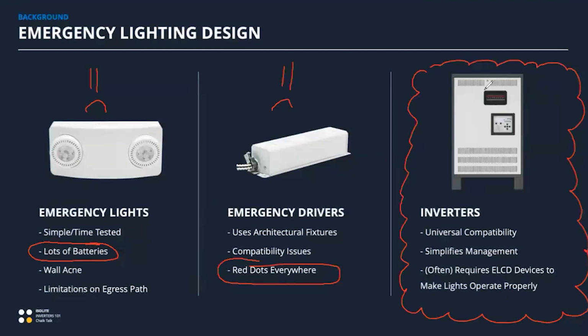And that really simplifies the management of a system. So instead of going and hitting all of these disparate batteries for maintenance purposes, this device becomes the one throat to choke of the life safety system. You have to go to one place to maintain your life safety system when you're using an inverter-based system.